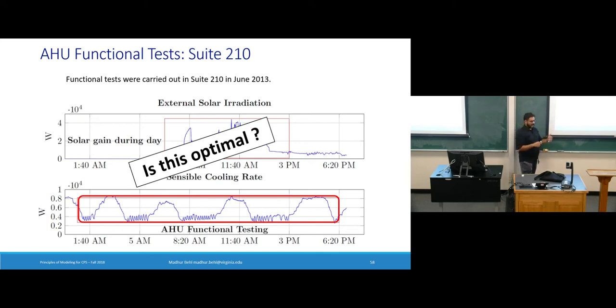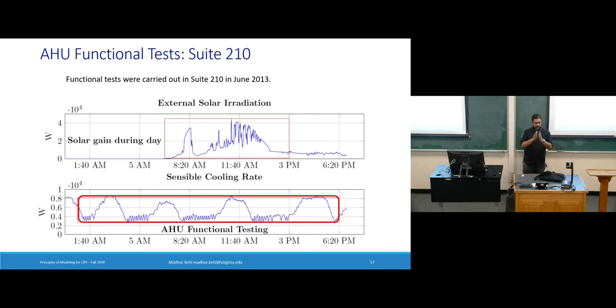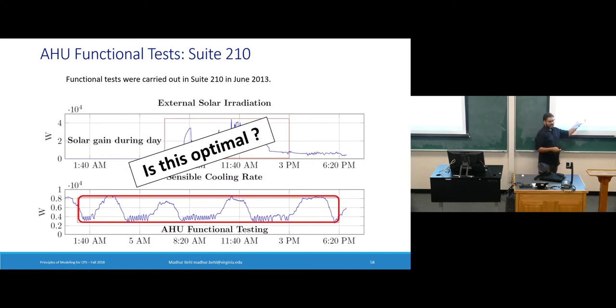There's a question here, because otherwise the remaining minutes aren't going to be that insightful. First, does everybody agree that if you train on data where nothing changes, it's not a very good model? Because anytime there's any change, your model will have a large prediction error. To fix that - I can't control the solar radiation outside, so for some control variables we artificially excite it. We do some pseudo-random, bang-bang control or input sequence injected into the plant to observe how the zone temperature output varies when there's a lot of excitation in my inputs. Does everybody agree that's necessary or a good idea in general? And the question is, on top of that, how do you decide what is the good sequence to excite your plant? That's the setting for the next 5 minutes.